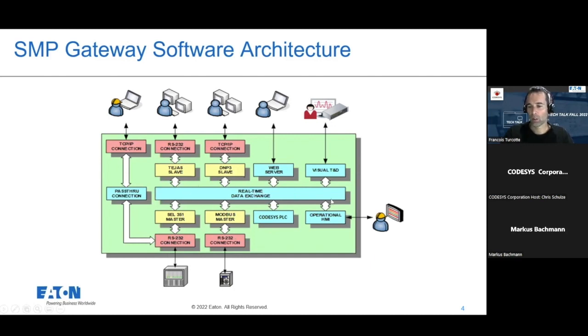That comes in the middle, where you can see that real-time data exchange is the middle, or I would say the centerpiece of all the communication between all the modules in the SMP gateway. All the values gathered by a master are then sent to that layer and transformed into just a point. We call a point just a value, a time tag, and a quality. So that's really just three simple values that each point represents in the system.